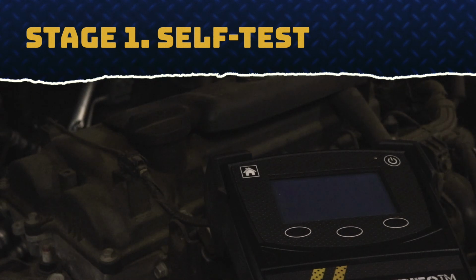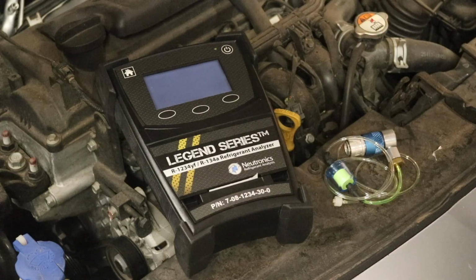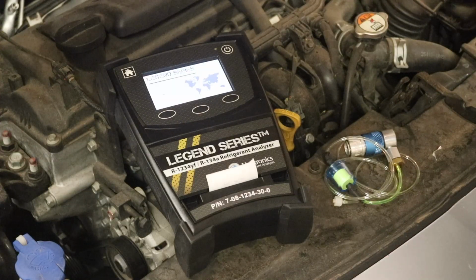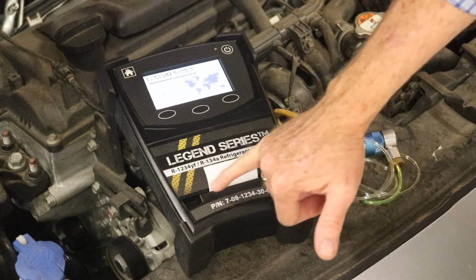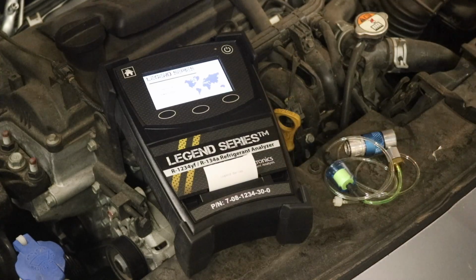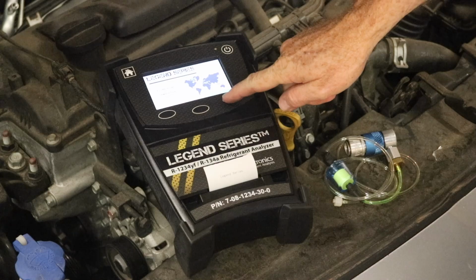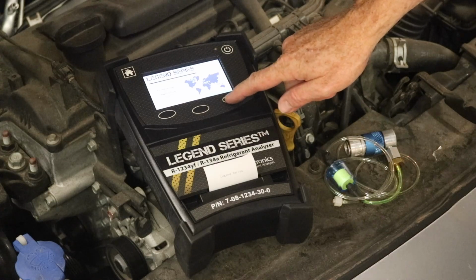The initial stage is a self-test stage. It's checking the software and firmware, and it will display the actual software and firmware values on the screen. And if everything is okay and it's happy with the circuitry and the resistance value through the actual sensor that it's going to heat, then it will come up with the screen lit and it will print Legend series on the printer to say we're good to go. After that, we get the option to hit next. So let's progress to stage 2.